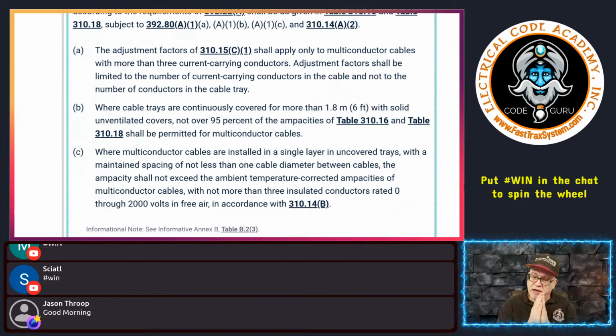It may be that your cable tray with an unventilated cover only goes through a fire penetration or through a fire rated wall or something like that where it has to be sealed. And you may have one piece that hooks into the tray that's designed to go through that penetrated wall, and maybe that's only a foot long or 2 feet long and that type of thing. Well, it's not more than 6 feet. That doesn't make a difference. But what if it was penetrating through it and it was 6 feet? Then this exception in 310.14(A)(2) may be a big benefit to you. It may help you. Okay, so I like to point those things out whether you use it or not, but that's why it makes the statement up here, because it is very much still in play.